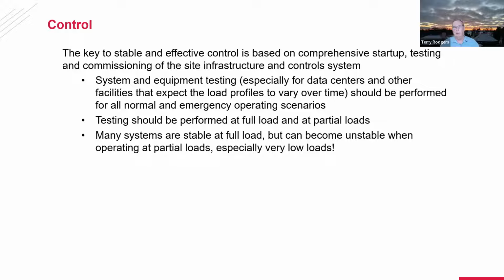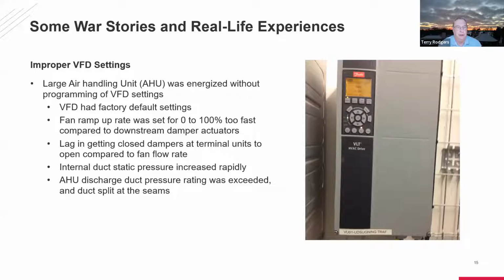But data centers and some factories and other things can ramp up, ramp back down, or they can increase over time as loads are added. And so a lot of times what happens is people come in and test it at the ultimate highest demand, the biggest load. And in reality, a lot of the control systems are most stable when they're under full load, like a chilled water plant, et cetera. It's when you have a very low load condition that the controls start searching and going into sine wave type things where they're overshooting, undershooting, et cetera. So loop tuning is very important. But especially, some systems like chillers can become unstable at very, very low conditions, et cetera. So it's important to test them at all ranges of expected conditions.